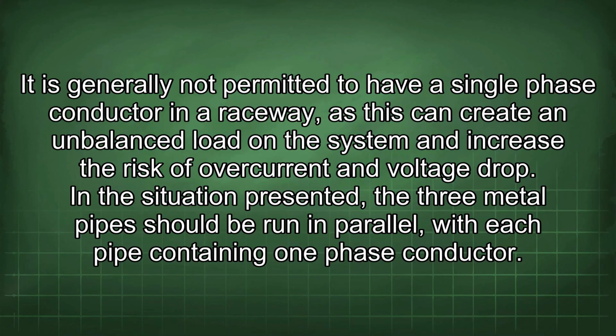It is generally not permitted to have a single-phase conductor in a raceway, as this can create an unbalanced load in the system and increase the risk of overcurrent and voltage drop. In the situation presented, the 3 metal pipes should be run in parallel, with each pipe containing one phase conductor.